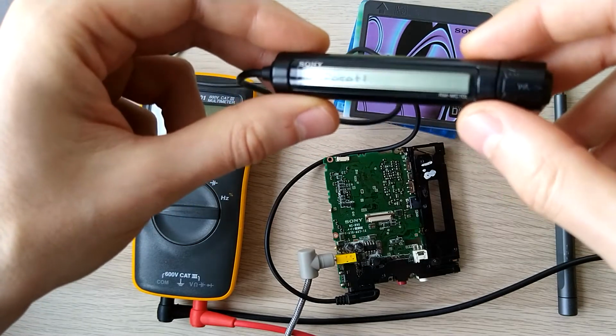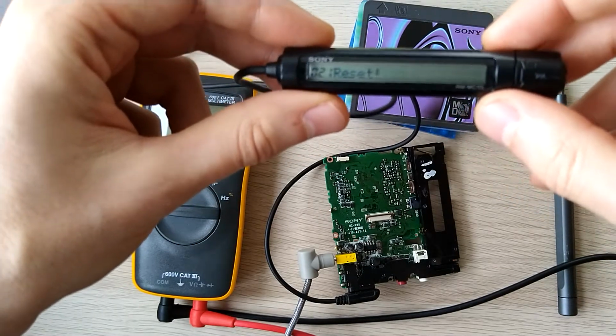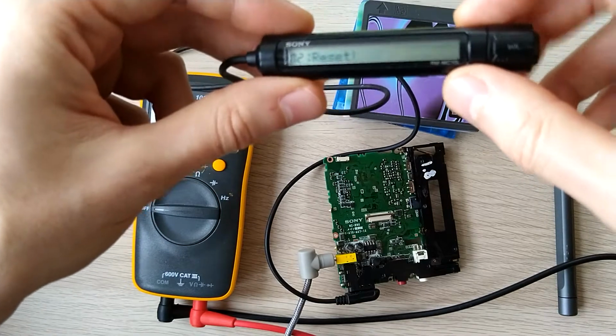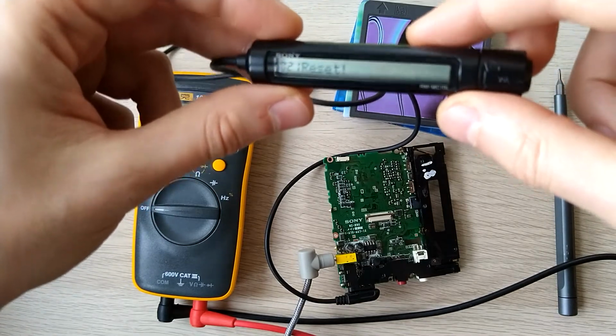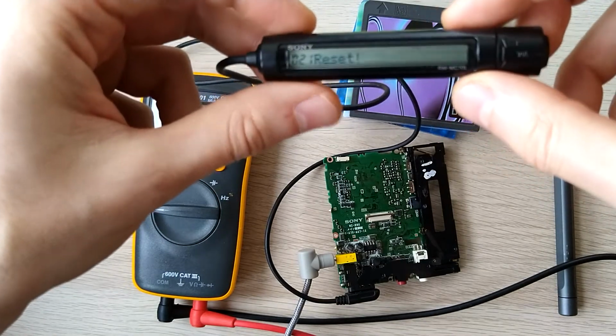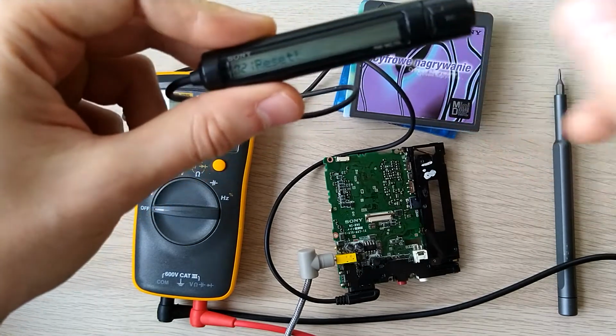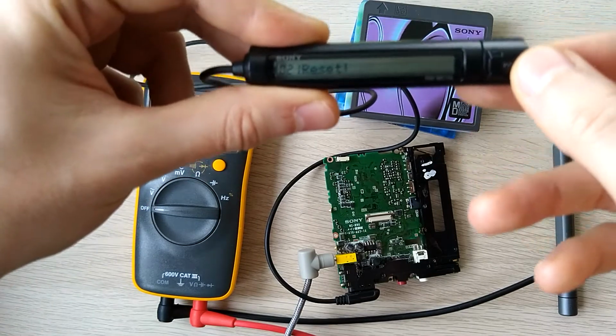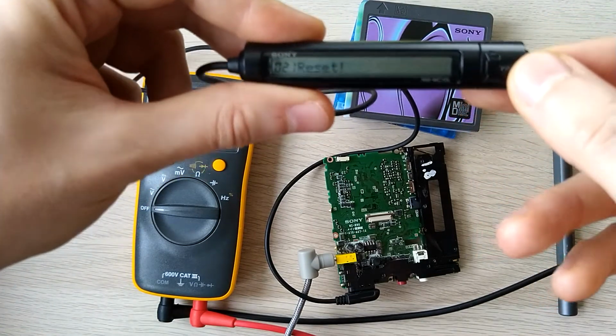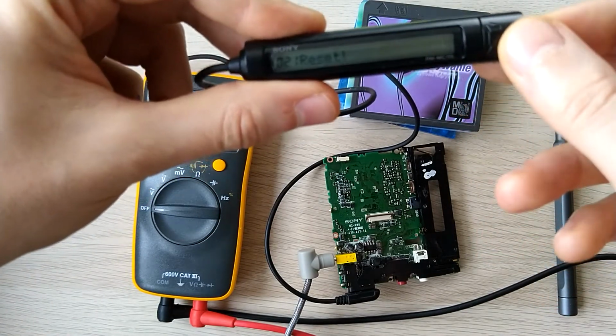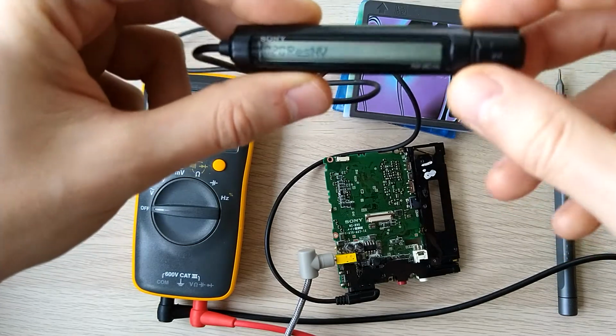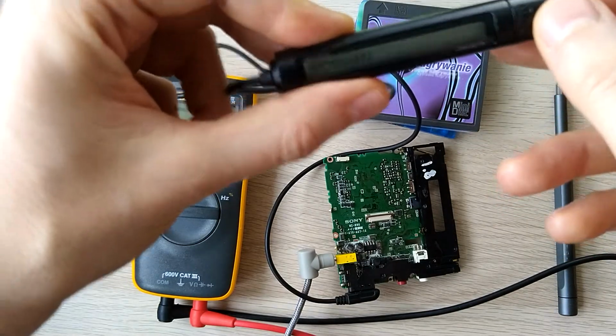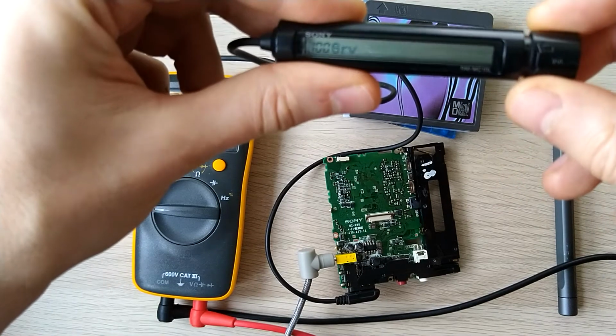Once you've done this, you have to go through the remaining steps of this procedure, otherwise the device won't work correctly. In fact, it will even refuse to start normally. It will just keep starting in service mode until the steps are finished. So once you have cleared the memory, we can move on to the power adjustments.